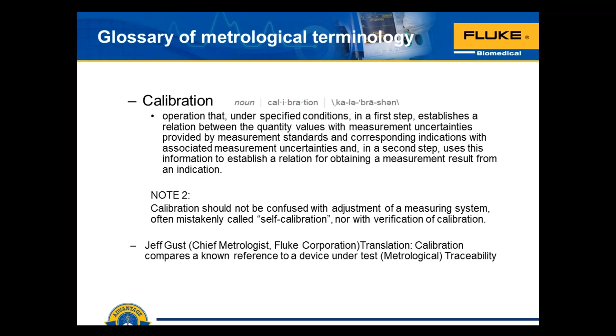Calibration adjustment is the adjustment of a measuring system, and this means a set of operations carried out on a measuring system, that's like our DMM or our electrical safety analyzer or our electrosurgery unit analyzer, so that it provides prescribed indications corresponding to given values of a quantity that is to be measured. So when we make an adjustment, either on our test instrument, which would be something that Fluke would do for you when you send it back to us for cal, or by you on a medical device in order to make sure it is operating within its specifications, and especially those that are tied back to the standards for minimum performance and safety, that calibration adjustment that you're making on that medical device should be a traceable measurement.